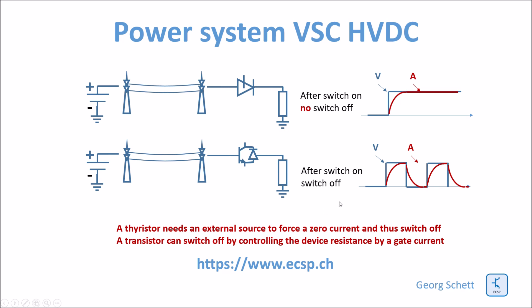When you have an active switch — an IGBT or transistor — the transistor can be switched on and the current flows, but then it can also be switched off again just by reducing the gate voltage from a few volts to zero. The resistance of the switching element then increases to close to infinite and the current goes back to zero very quickly. Therefore, with VSC you can synthesize an oscillating output waveform, which is not possible with the thyristor.